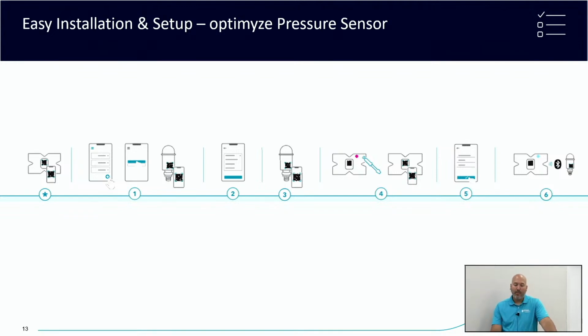So once you click that, a pop-up should show up asking you, what are you adding, an Optimyze sensor or a pressure sensor? You're going to click pressure sensor. It's going to ask you to scan the QR code that's on the pressure sensor. Depending on what you pick, if you're just picking suction pressure or discharge pressure, it's going to jump to step 4. But if you select differential pressure, it's going to ask you then to scan the QR code of the second pressure sensor that you're going to be installing in the application.